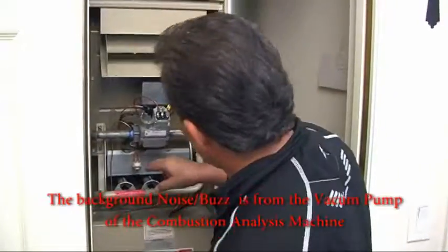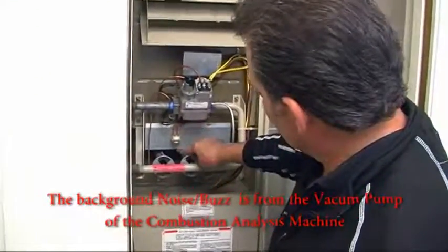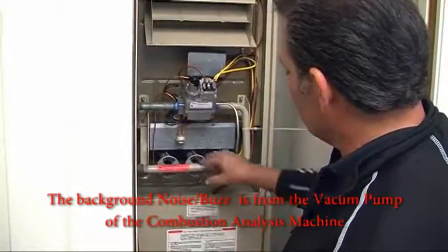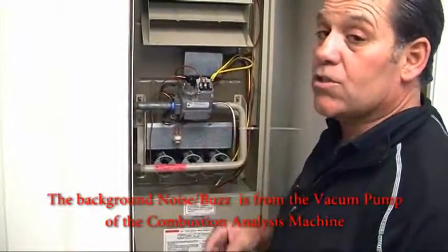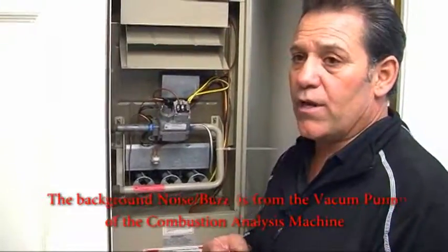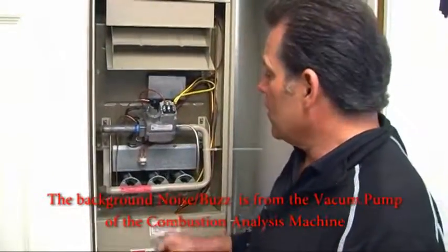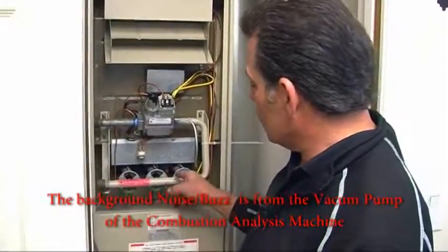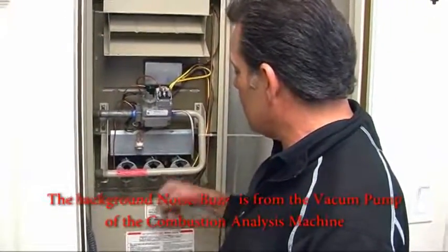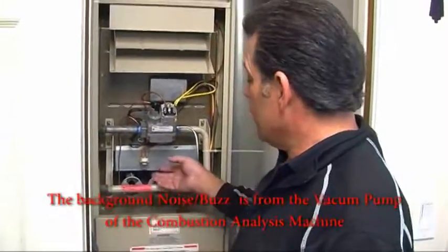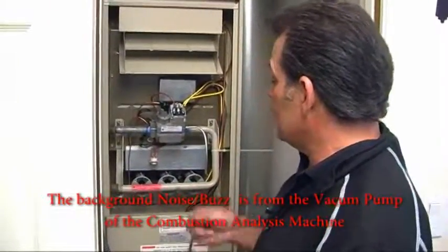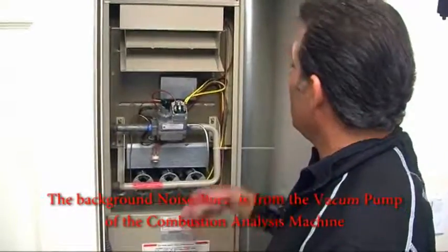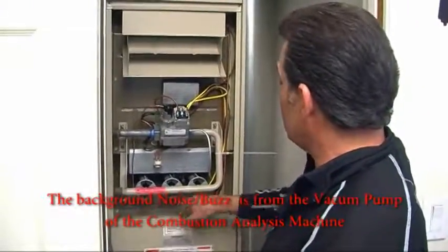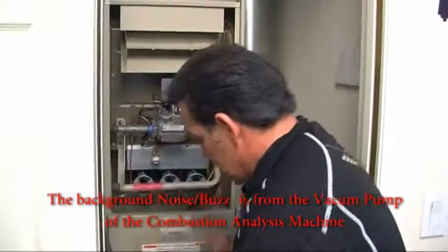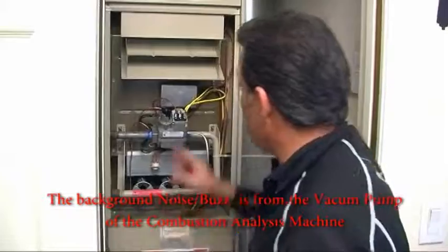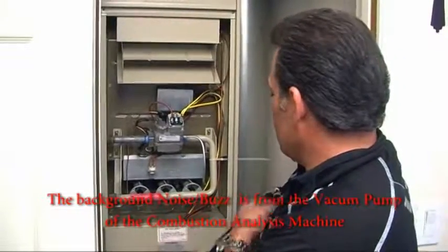From here, we run down to our flame rollout switch. This is a one-time fuse rollout switch. If the flame does roll out from the heat exchanger, it's looking for oxygen. In order to create combustion and to keep combustion, you need 3 things. You need a fuel source. We have that. We have an ignition source. We have our pilot lit with the thermocouple keeping it lit, and then you need oxygen. So if you ever have to replace this switch, you know that you have a problem with either your combustion air not getting into this area here and into the burner chamber through the grills, or there's something blocked in the vent which is keeping it from creating combustion.